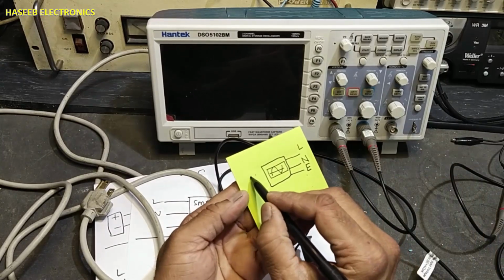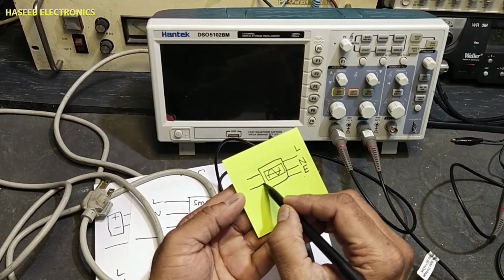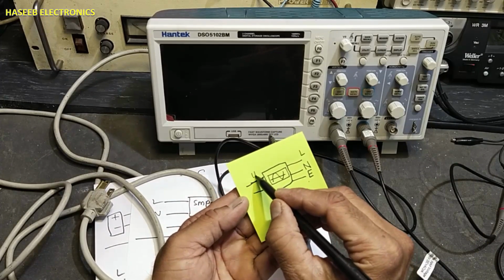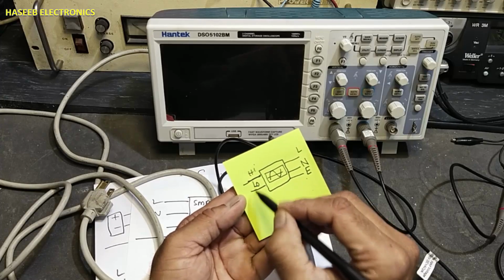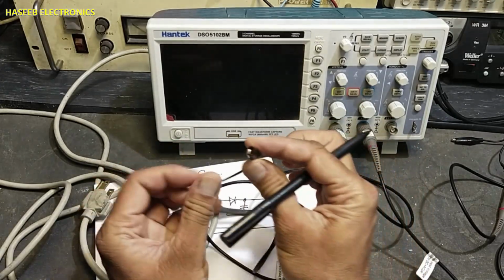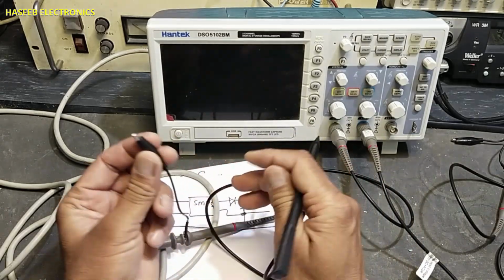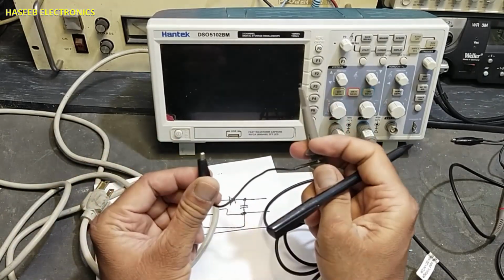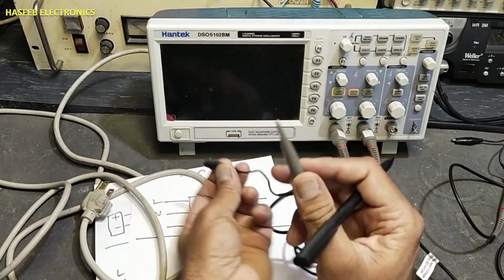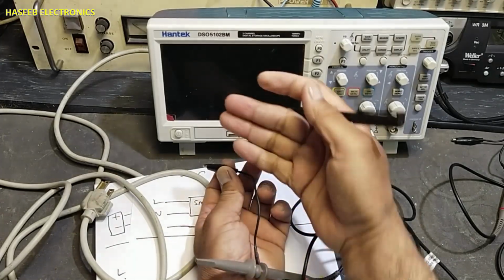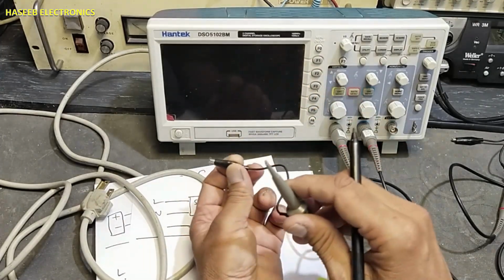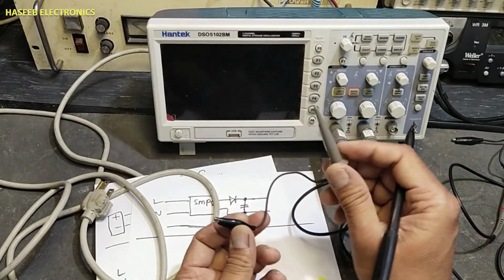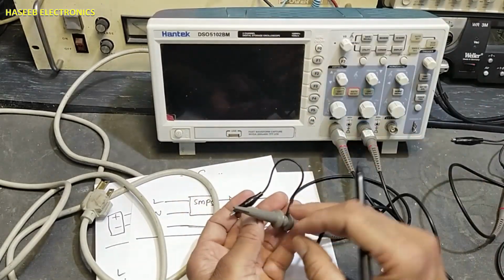And we have two test leads, high and low. This test probe is ground, low side, and this is high side. We can connect this to high, this to low, and it will give an inverted signal. If this is low and this is high, it will give a direct signal in the positive direction.